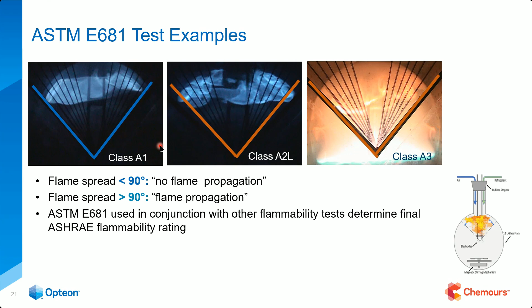So let's take this relationship between flammability and GWP. I want to compare 404A to 454A. First, in order to lower the global warming potential, we have to get rid of the chemicals causing that inside these blends. Unfortunately, some of those chemicals were what made them non-flammable. For example, 404A is 44% R125 and 52% R143A.